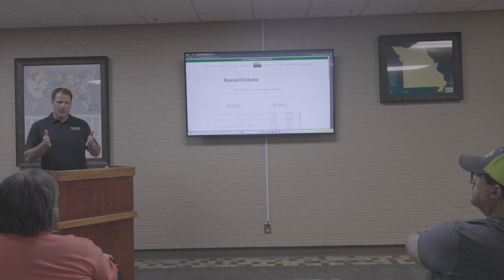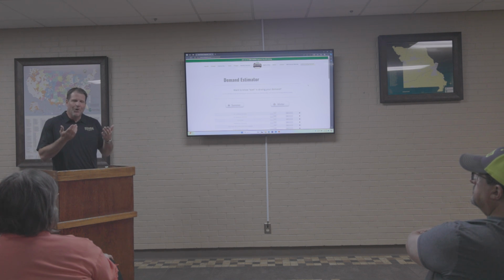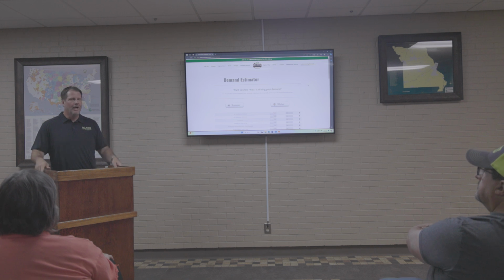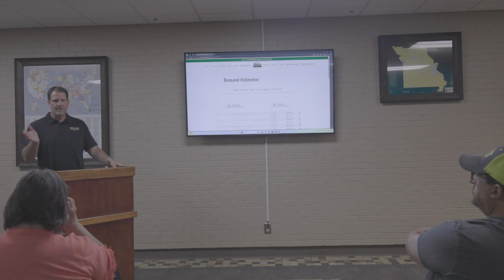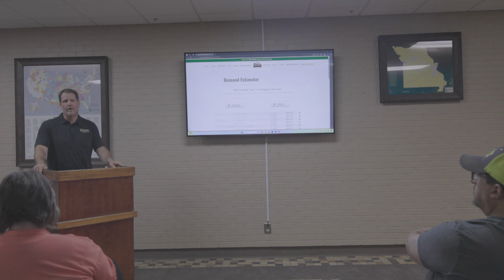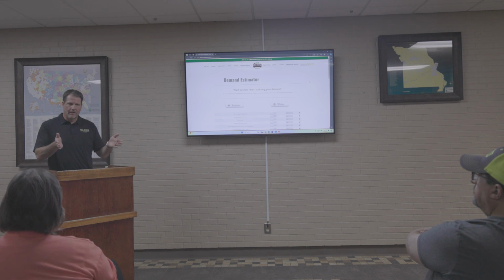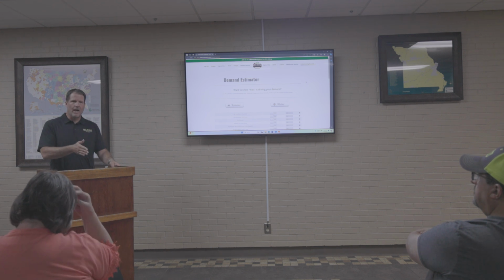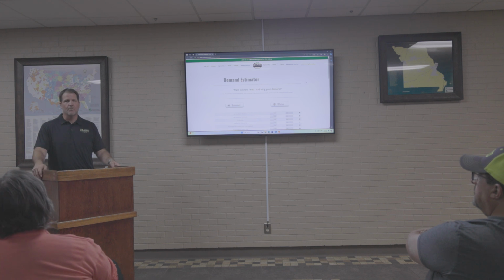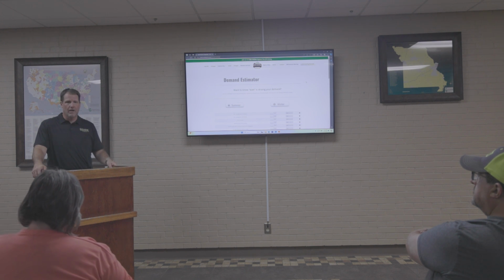That allows time for something to clear, whether it's a squirrel that's out there, whether it's maybe something that's interfering with that, maybe a limb that's been blown into it or something like that, or even in a vehicle accident case, there's a momentary lapse where something can clear itself. So if it clears itself, it comes back on. If it happens 3 times, on the 4th time it goes completely out. So that's when a lot of times maybe it blinks a couple of times before the electricity comes back on. That's when that would happen. Typically there aren't surges involved during that, but everything does ramp up and come back on.